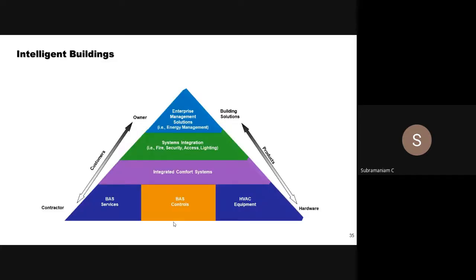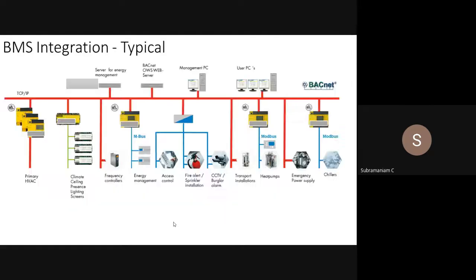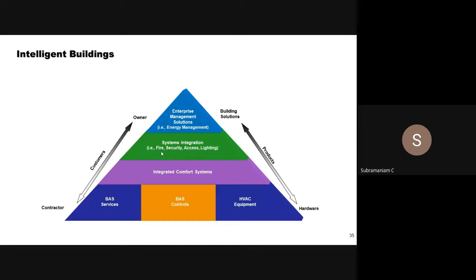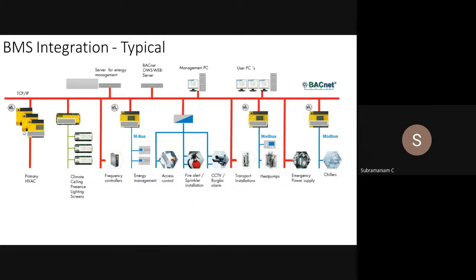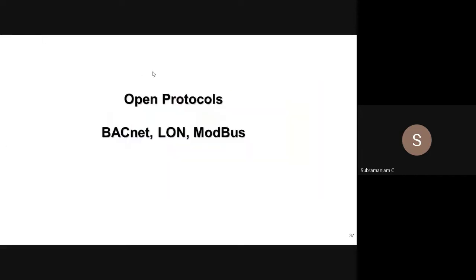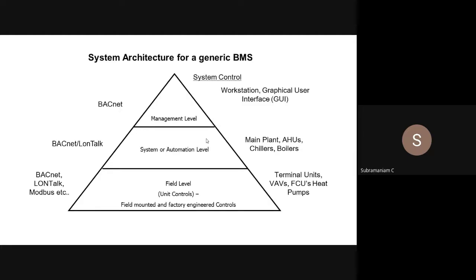So going forward, on the protocol. The BMS is going to interface with a lot of other systems also: fire, security, access, lighting. So you will have various things at the ground level, and then they all get integrated. When we talk about protocols, there are BACnet, LON or Modbus. These are the three common protocols. So what is BACnet? What is Modbus? What is LON? We will see.